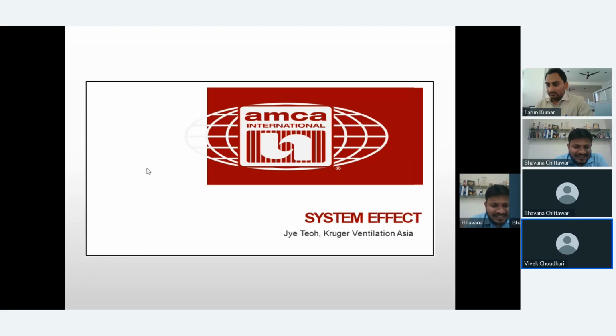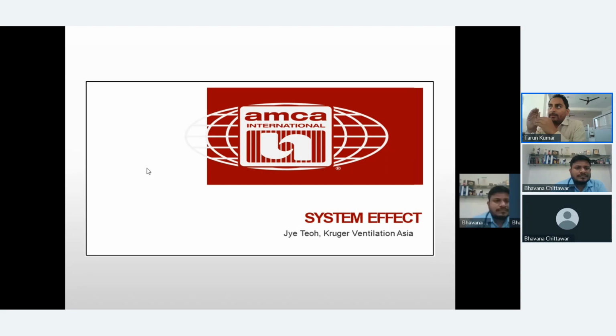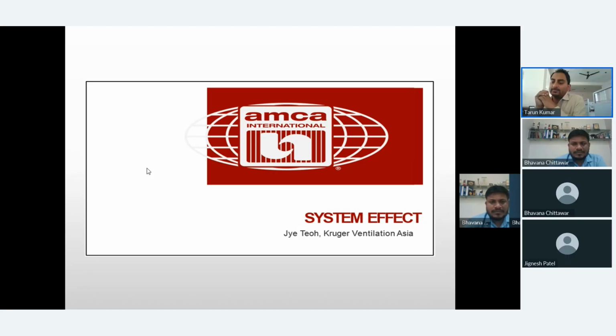Right, sir. Okay. Then another question: mention the construction difference between forward curve and backward curve fan. Forward curve, construction-wise, has multiple blades and is made up of GI, whereas the backward curve fan impeller is made up of MS. So backward curve always has more static carrying capacity, and forward curve has lesser static carrying capacity. That is the major difference between the forward curve and the backward curve.